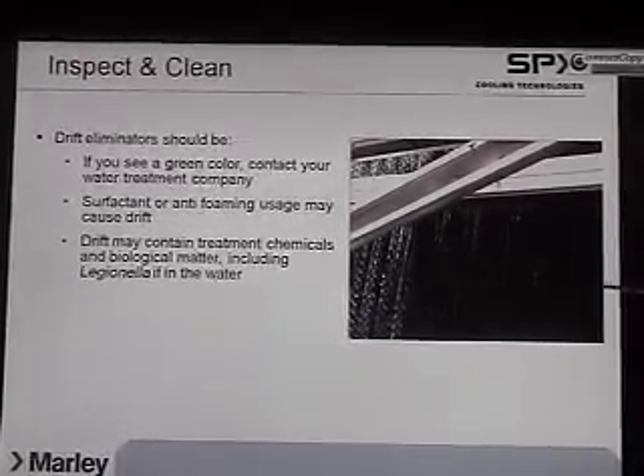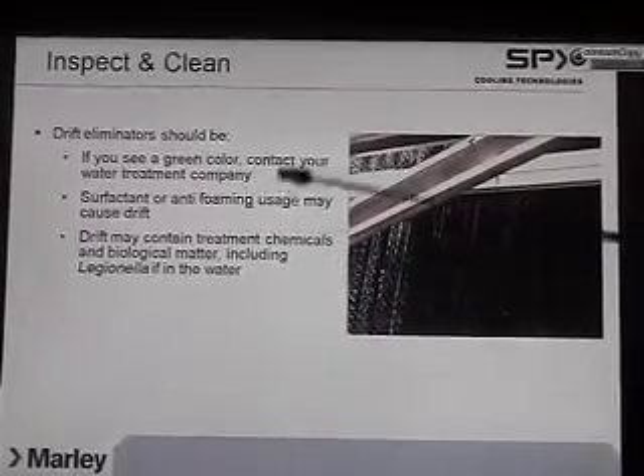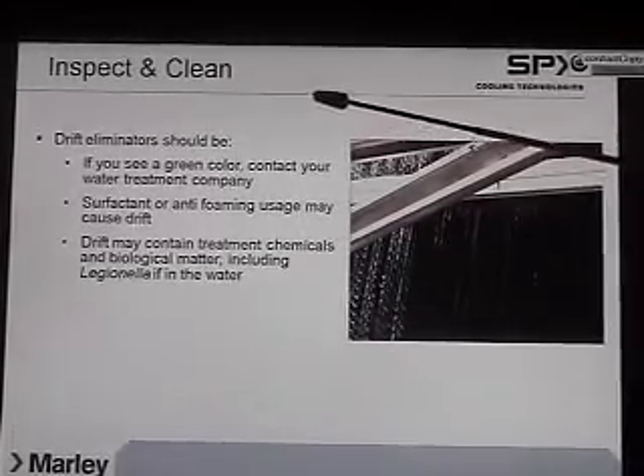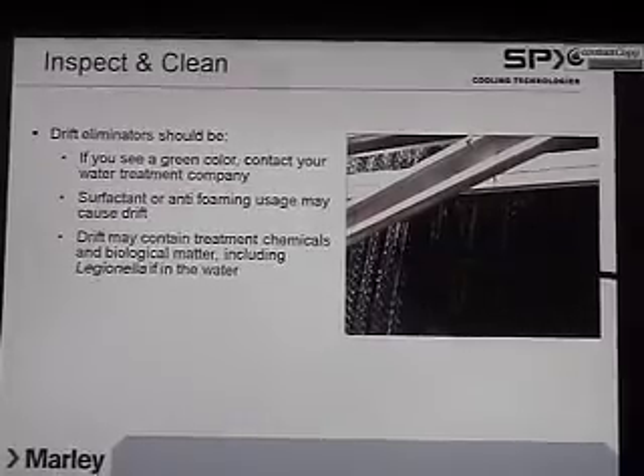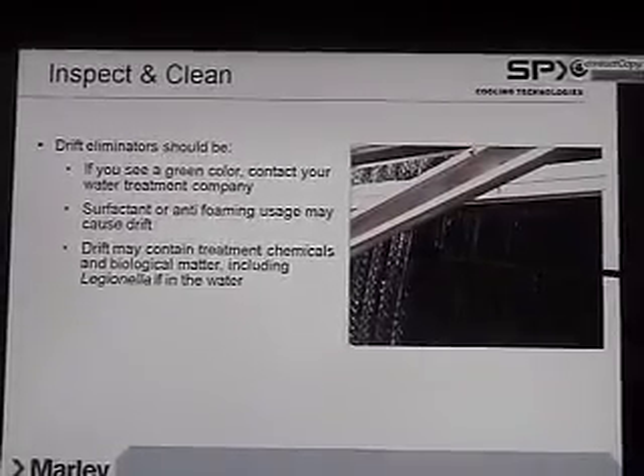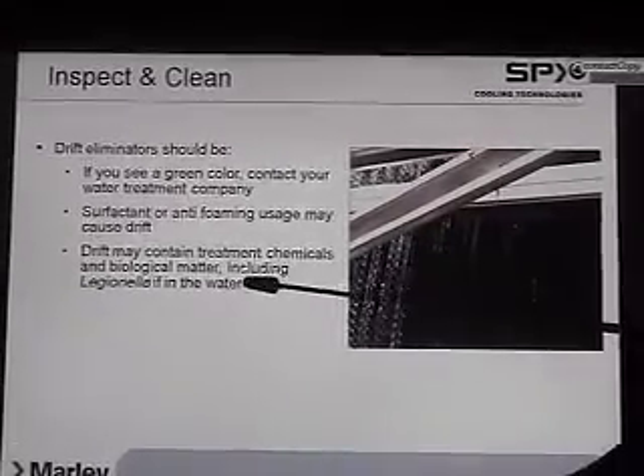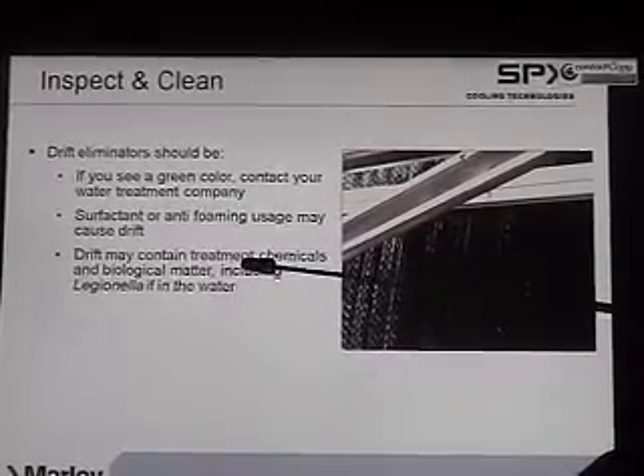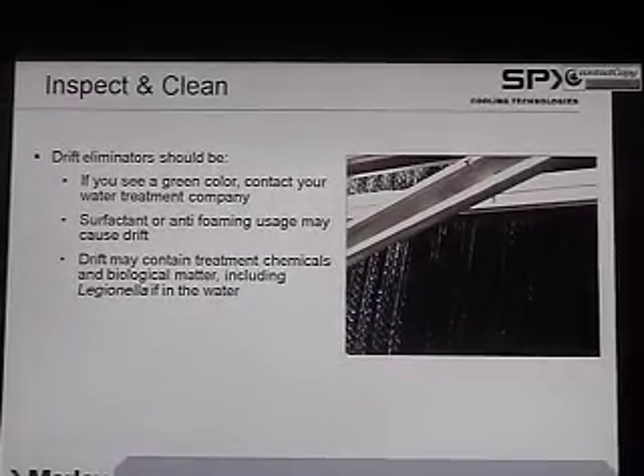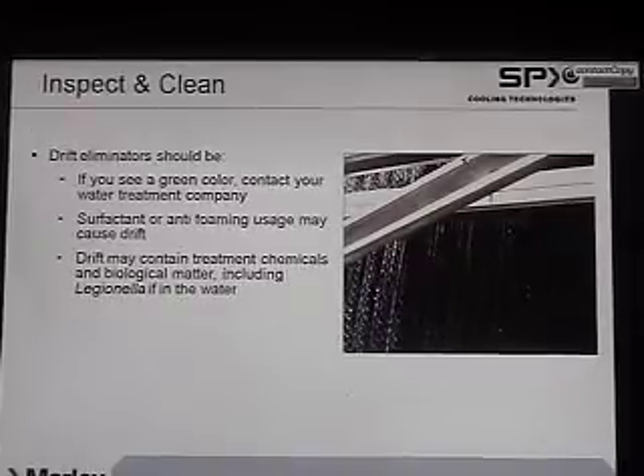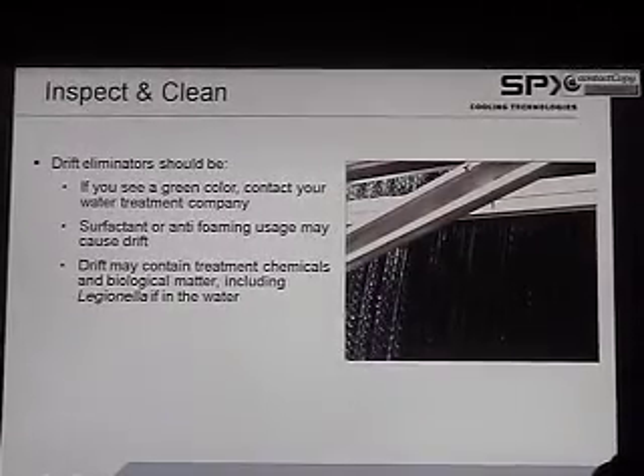The drift eliminators in your tower are located right above the water distribution system. They're about 4 inches thick, and you would need to place some sort of piece of plywood or something on there, and then you could stand on them after you lock out the tower.